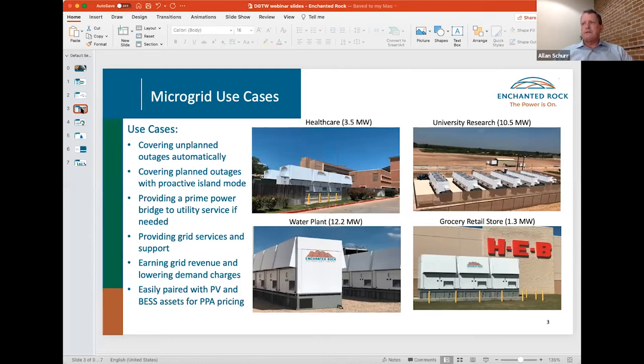Continuing clockwise, a retail grocery store, HEB—if you're not familiar with them, they're a very large Texas grocery operator. This is a typical system we install at HEBs: 3 generators, 1.3 megawatts of power. Given the loads of an HEB, as is the case with most of our microgrids, we have an N+1 design so that if we're doing maintenance on any particular generator, we can still cover the entire load of the facility if there's an outage.